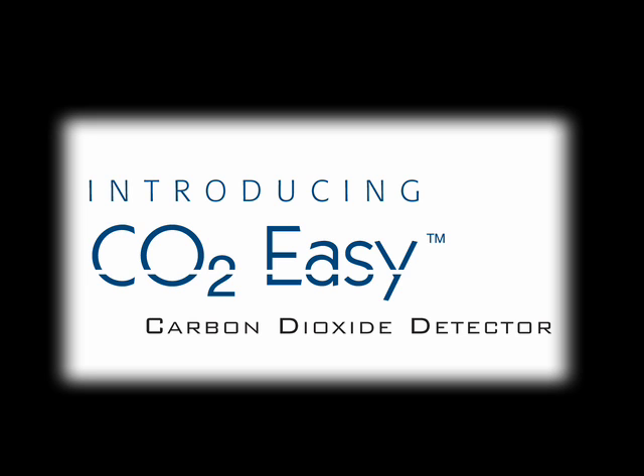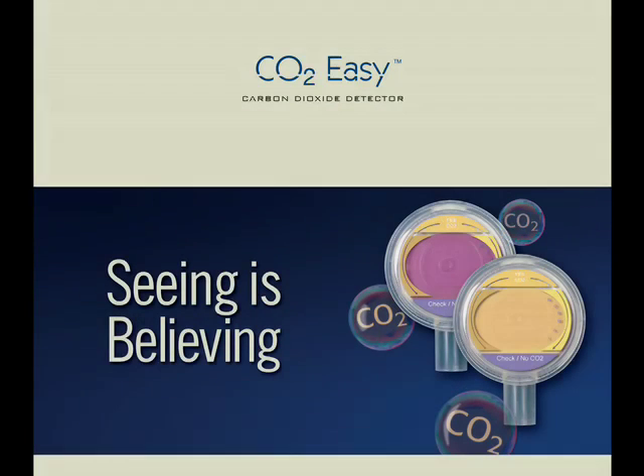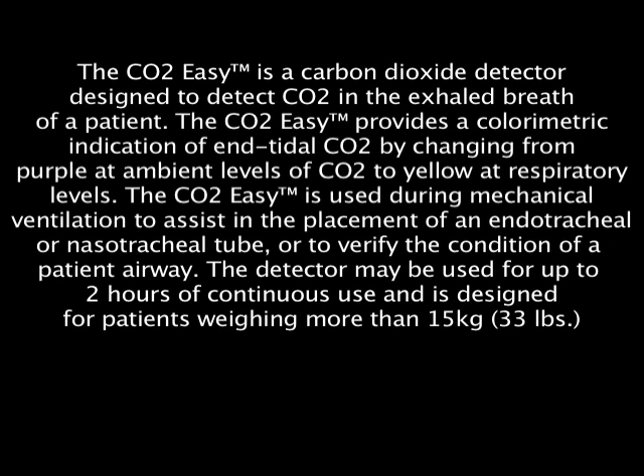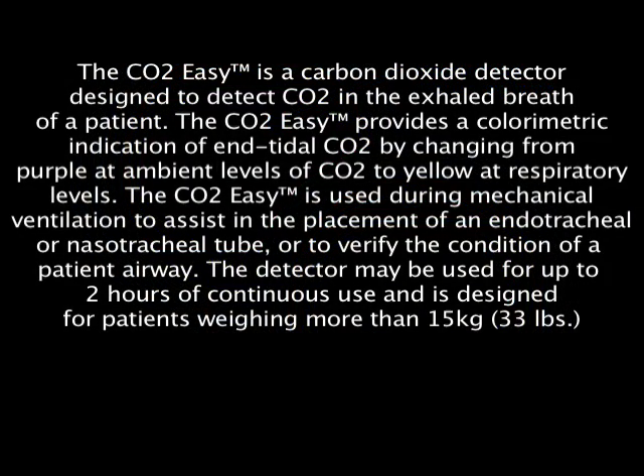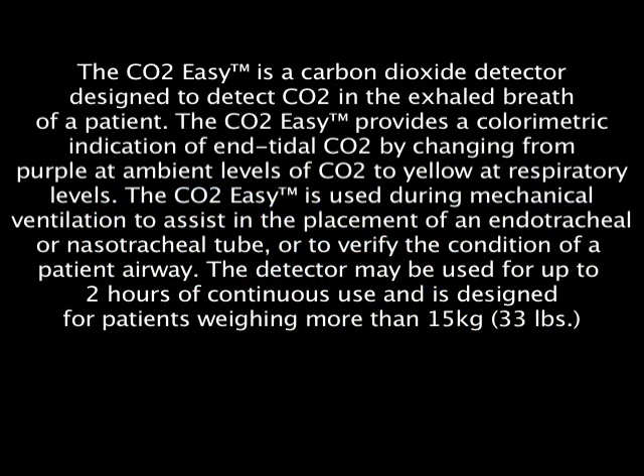CO2 Easy is a carbon dioxide detector designed to detect CO2 in the exhaled breath of a patient. The CO2-Easy provides a colorimetric indication of end-tidal CO2 by changing from purple at ambient levels of CO2 to yellow at respiratory levels. The CO2-Easy is used during mechanical ventilation to assist in the placement of an endotracheal or nasotracheal tube or to verify the condition of a patient airway. The detector may be used for up to two hours of continuous use and is designed for patients weighing more than 15 kilograms or 33 pounds.